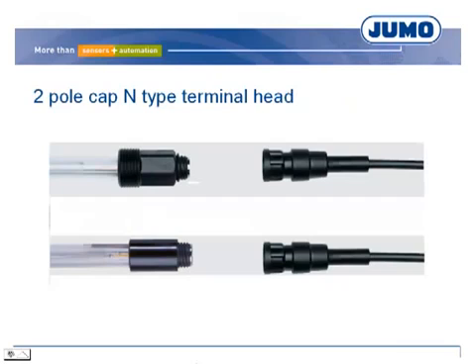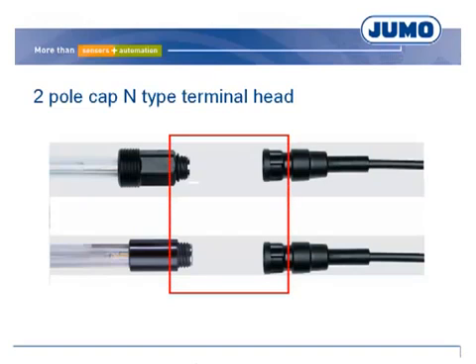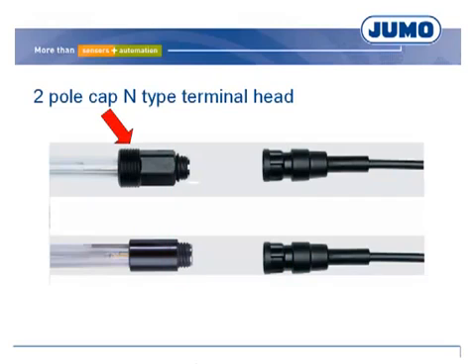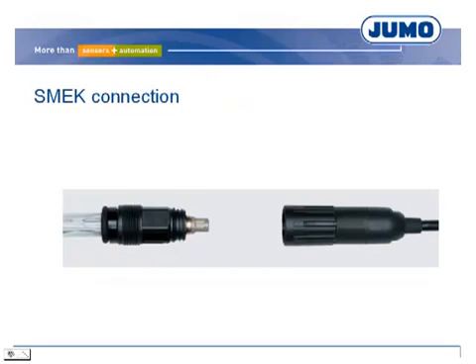When the combination electrode does not have a resistance thermometer, the connection is realized via a 2-pole cap N-type terminal head. Combination electrodes are fixed into fittings with a PG 13.5 male thread. For laboratory applications, the electrodes are also available without male thread. Generally, pH combination electrodes with an integrated resistance thermometer are available, using a 6-pole connection system called JUMO SMEK.